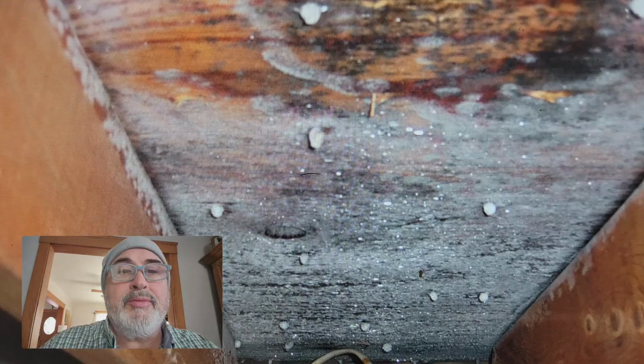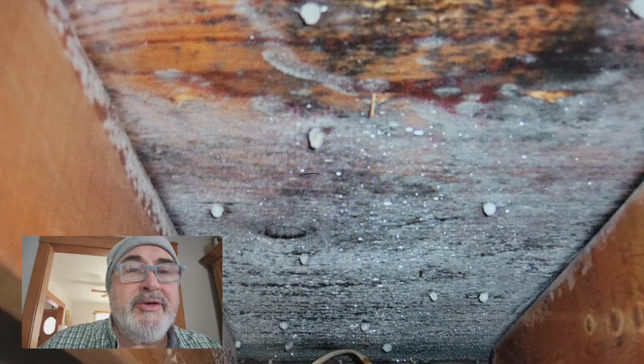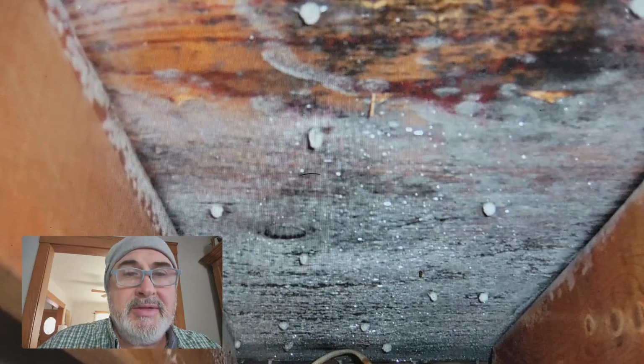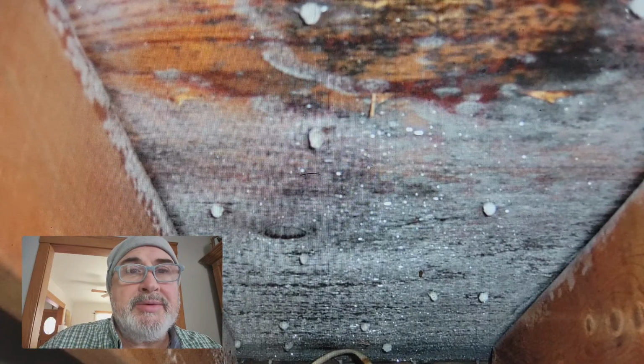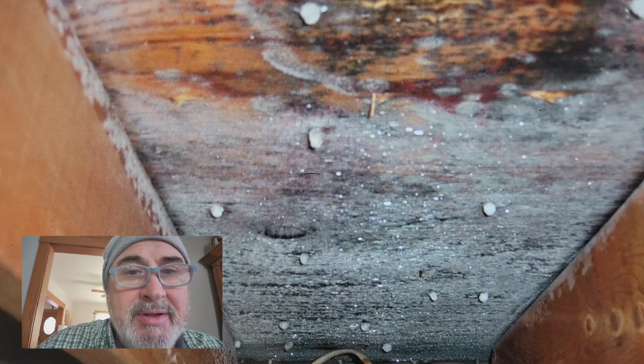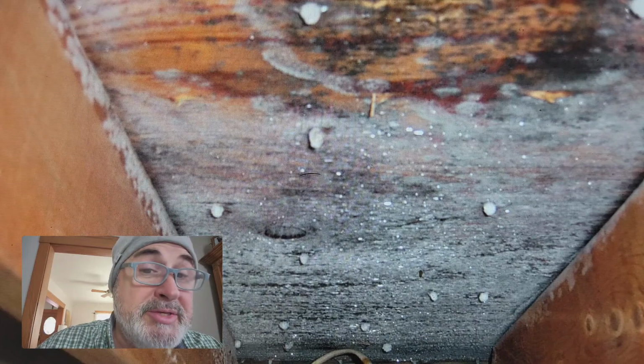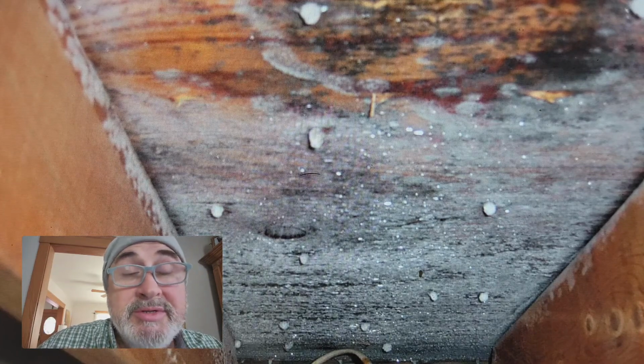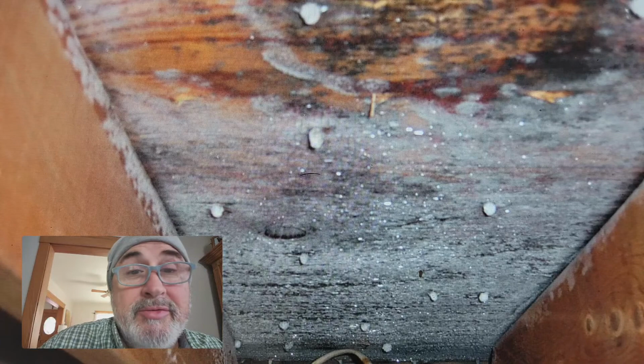Because they have a thermal bridge, and the R value is bad, so humidity in the attic ices up. So how is the humidity getting in the attic? Well, there's a whole bunch of videos on that, but usually 90% of the time it's either a ventless unit in the house, ventless heater, ventless gas fireplace, or a humidifier, or a crawl space that leaks that doesn't have a vapor barrier. Those are the 80% of the time it's one of those three.